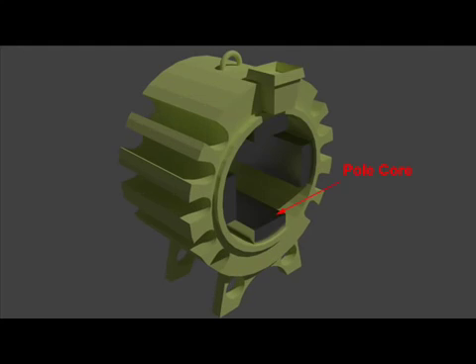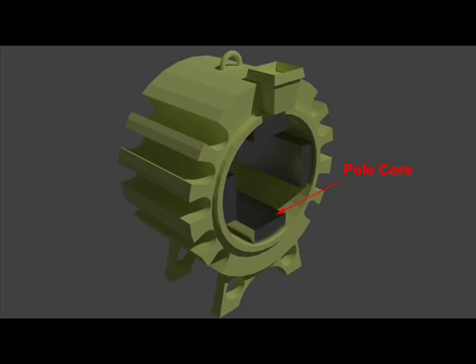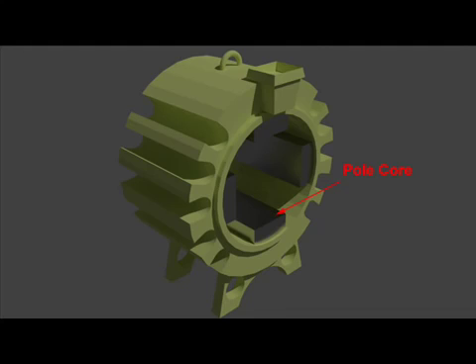The pole core of a DC machine is usually of circular section and is used to carry the coils of insulated wires carrying the field current. Pole cores are usually not laminated and generally made of cast steel. In some cases, these pole cores are laminated and composed of electrical grade steel sheets of about one millimeter thick and insulated with each other.